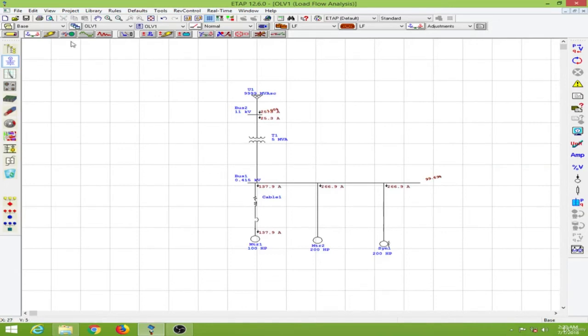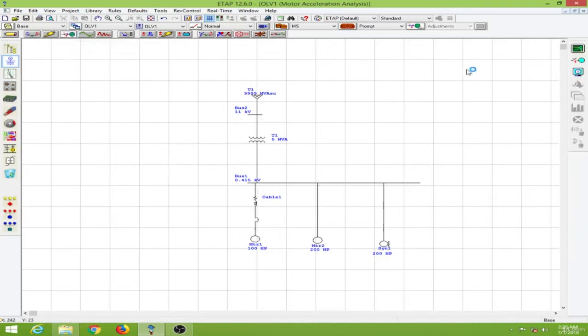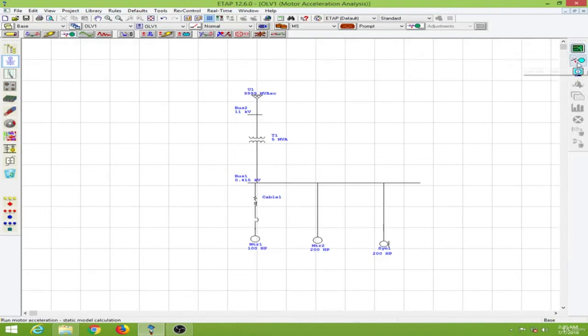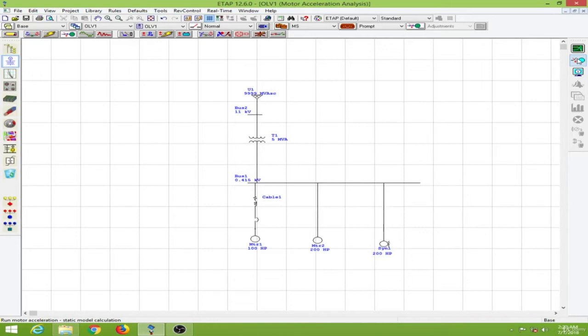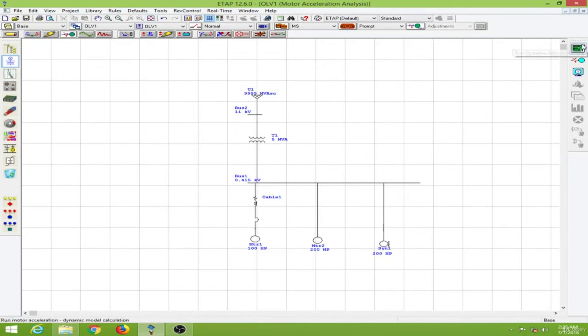Now going to the motor acceleration analysis tab over here from the mode toolbar. Now as you can see on my right side I have two analysis options over here. So we have the dynamic motor starting over here and the static motor starting over here. So the difference between the two is in static motor starting you don't have to provide the dynamic model of the motors or the synchronous motors that you have used in the simulation. So what you will get is a steady state response.